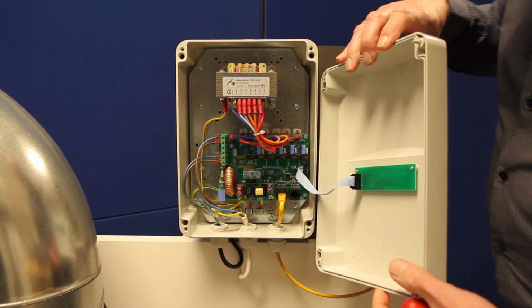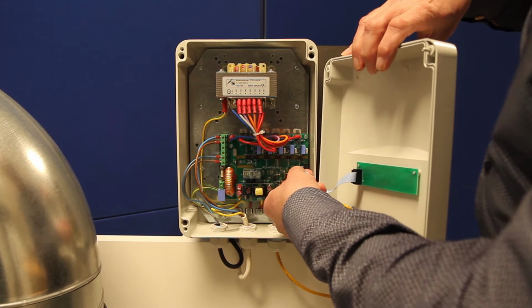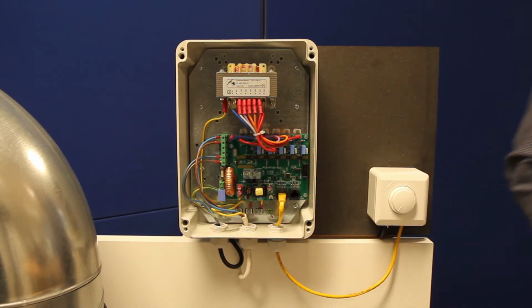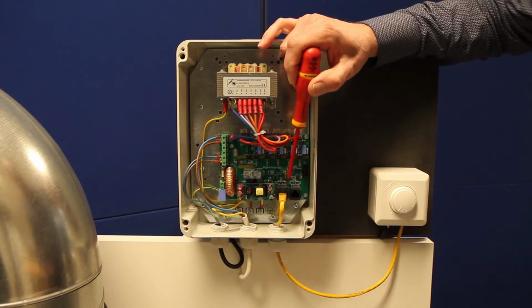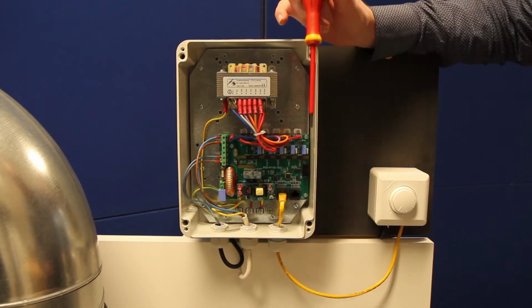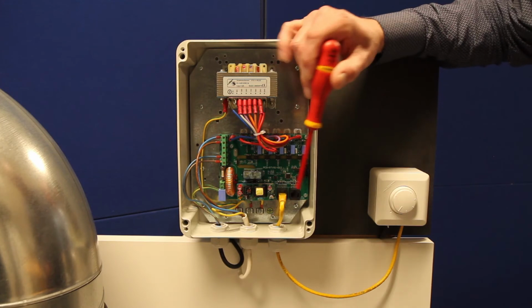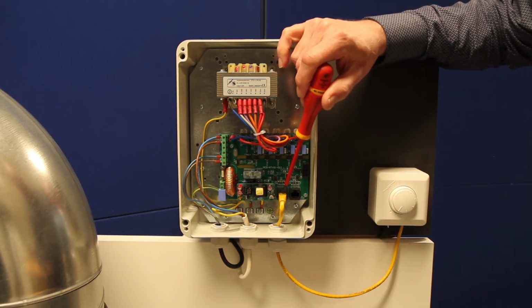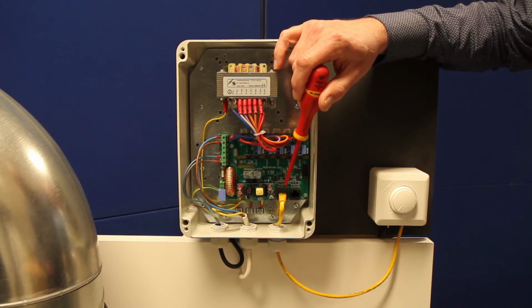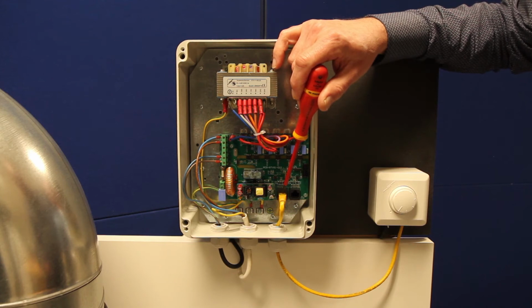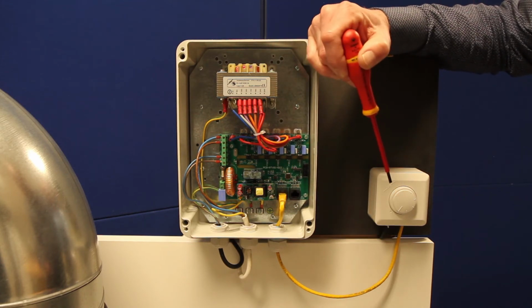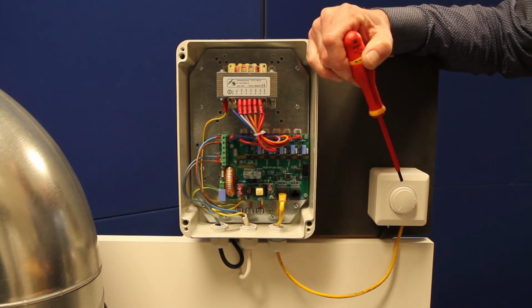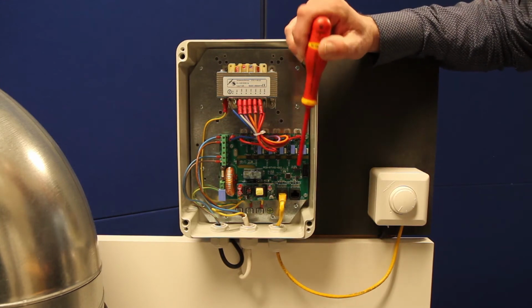When you open the device, pay attention to the flat cable. At the bottom of the PCB, you will see two RJ45 connectors. If you want to work with a demand-based control or a Modbus potentiometer, you will connect this to the left RJ45 connector.